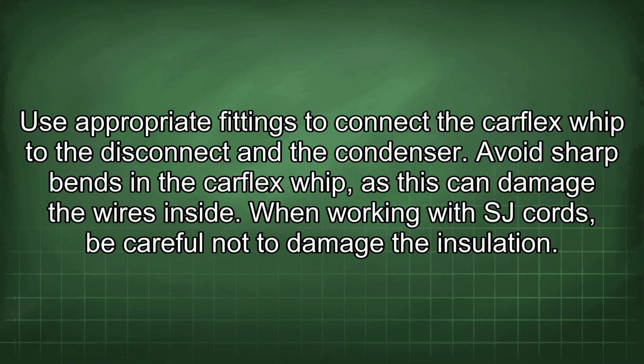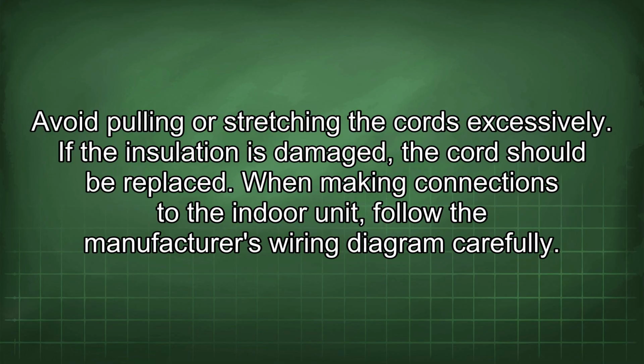Use appropriate fittings to connect the carflex whip to the disconnect and the condenser. Avoid sharp bends in the carflex whip, as this can damage the wires inside. When working with SJ cords, be careful not to damage the insulation. Avoid pulling or stretching the cords excessively. If the insulation is damaged, the cord should be replaced.